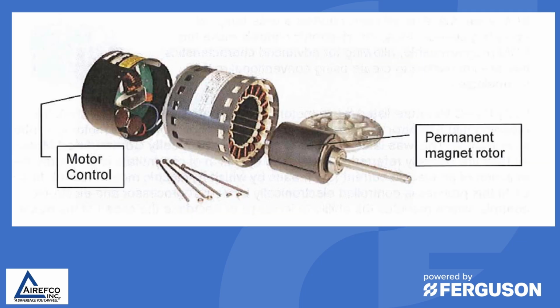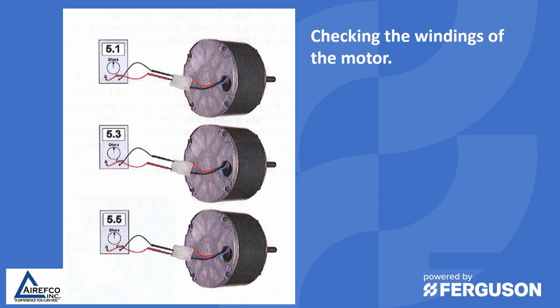So the ECM motor on most modern gas furnaces consists of a motor body that has the windings and then a permanent magnet rotor that rotates in the middle of it. And then the motor control, or the electronics, are on the back end of that ECM motor. Since the introduction of ECM motors in gas furnaces, there have been very few motor failures themselves. Most of the failures on ECM motors are the electronics in the back end of the motor.